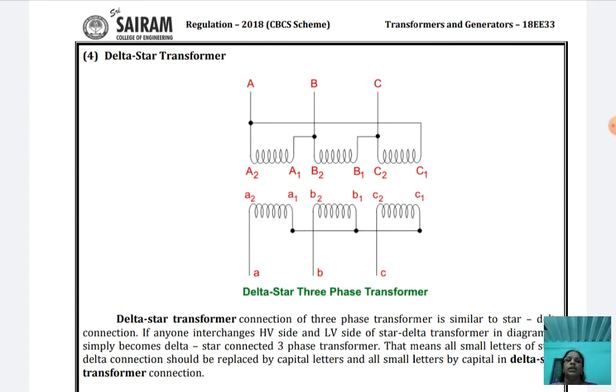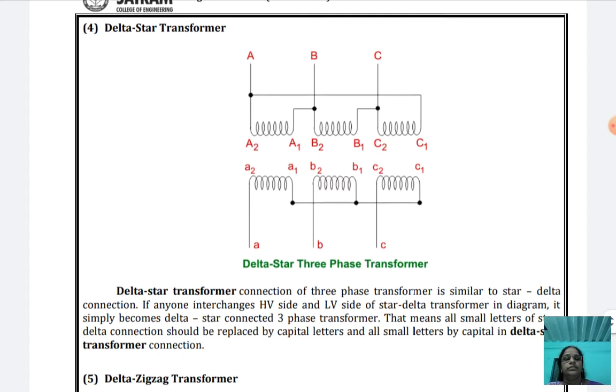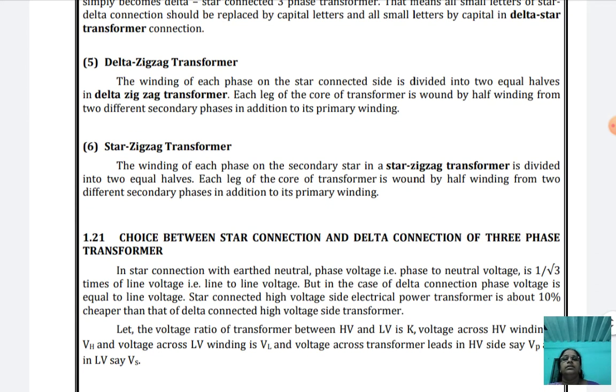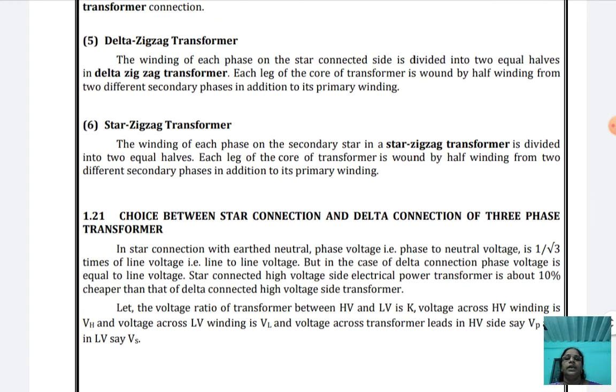So, the main thing you remember: the capital letter represents the HV winding, the small letter represents the LV winding. That means the HV winding is labeled with a capital letter, the LV winding with a small letter. The next, delta zigzag transformer, is also the same, and star zigzag transformer is also the same. The HV winding and the LV winding.